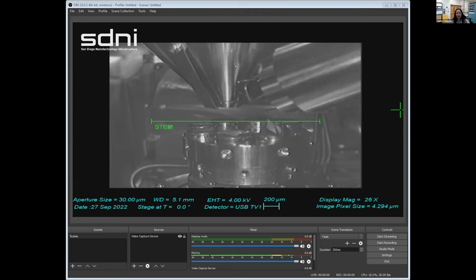The resolution of SEM is technically limited by the wavelength of an electron, but for practical reasons, it's more limited by the electron-sample interaction, since SEM samples have to be able to conduct electrical charges to some extent. We are able to look at samples, as you'll see in the live session, that are not naturally conductive, because we can sputter coat the samples with metal so that you can see them in the SEM.